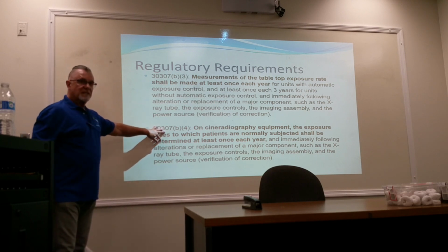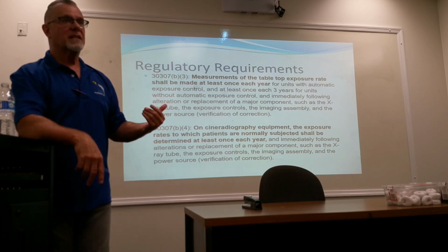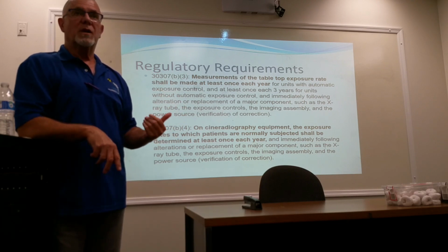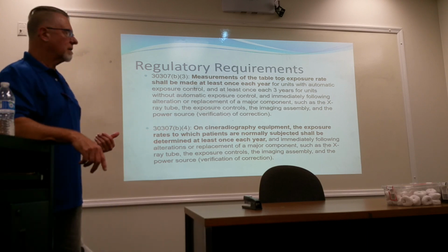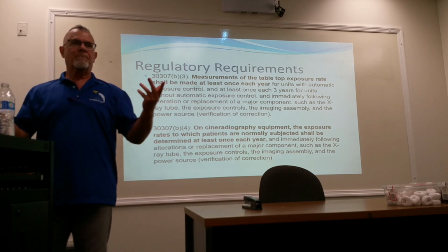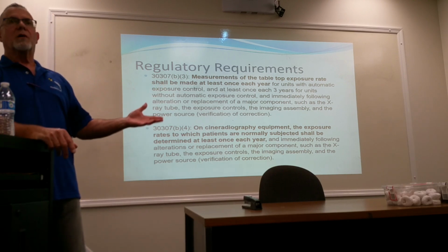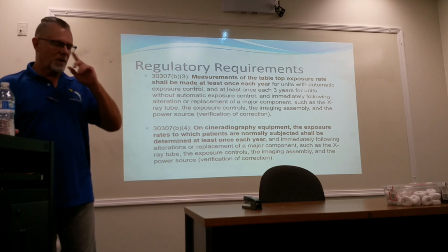So the state, since this is still old language, is referring to cine as in what we used to do with 35 millimeter film, which was very high doses to our patients, very high. In the digital world, they said, well, it's digital fluoro, it's all pulse, so you have to measure it in every pulse mode. And we said, no, wait.